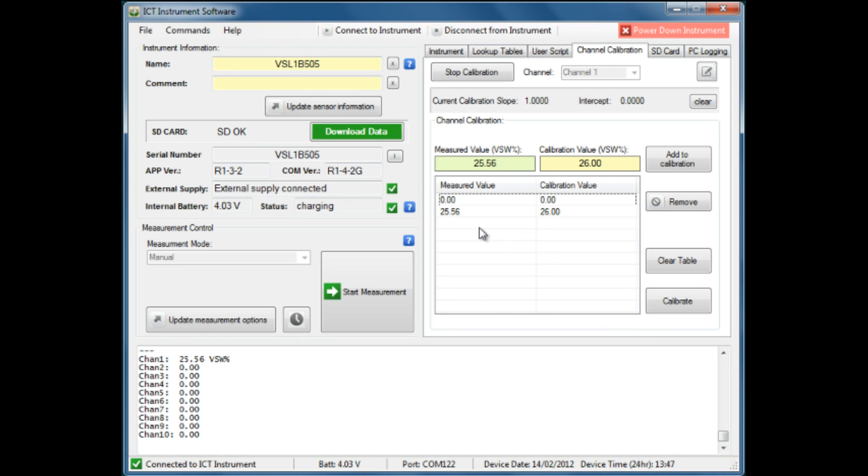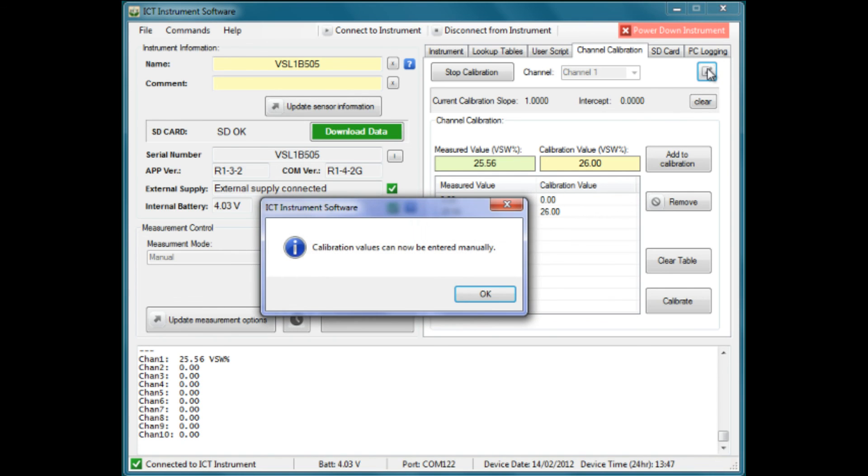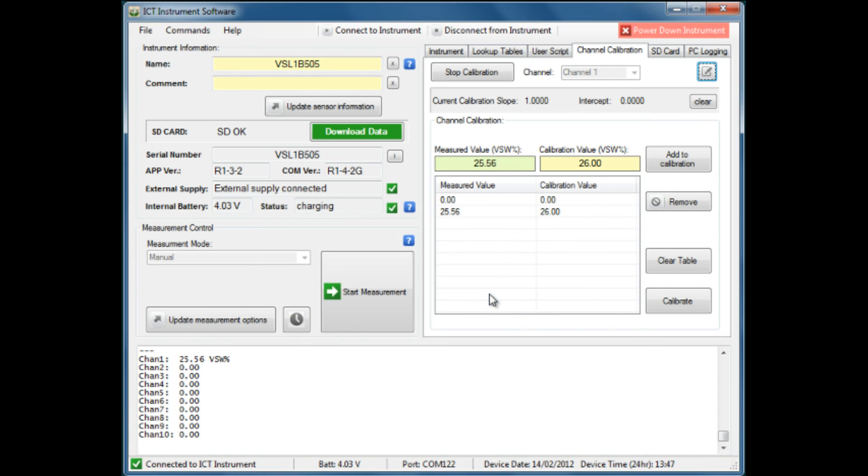What we'll do now is manually enter our third set of values. We once again go up to our pencil icon and are able to manually enter values. We will put in the value of around about 96 and use that relationship we have found earlier to have a corrected value of 97.65. We add that to our calibration, and that then becomes our calibration table.